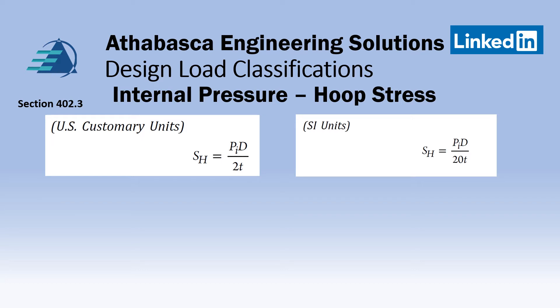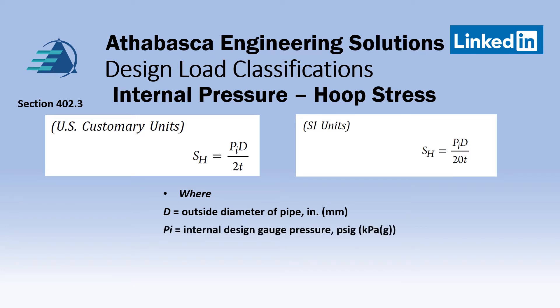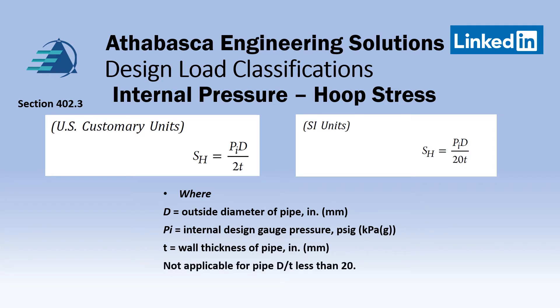Section 402.3 defines hoop stress from classical equations as the outside diameter of the pipe times the internal gauge pressure, divided by the wall thickness, divided by two. Two equations are shown — one for customary units and one for SI units. Note that these equations are based on classical equations for thin-walled membranes. There are two sets of rules — thick walls and thin walls — so when D over T is less than 20, these equations are not applicable.